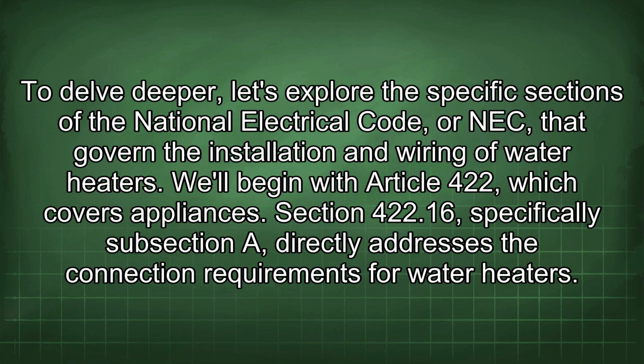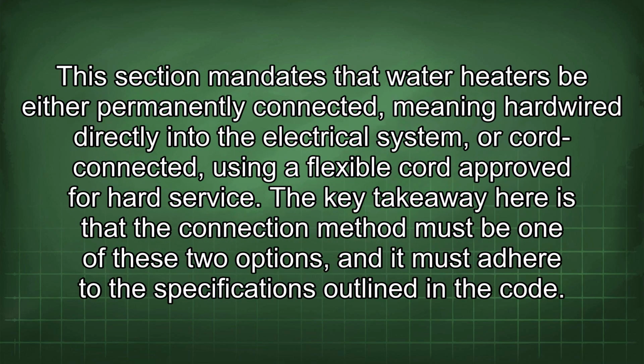We'll begin with Article 422, which covers appliances. Section 422.16, specifically subsection A, directly addresses the connection requirements for water heaters. This section mandates that water heaters be either permanently connected, meaning hardwired directly into the electrical system, or cord connected, using a flexible cord approved for hard service. The key takeaway here is that the connection method must be one of these two options, and it must adhere to the specifications outlined in the code.